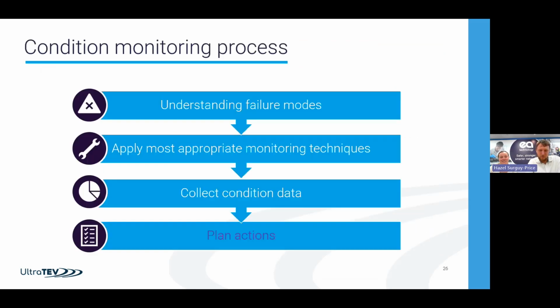The final and most important bit is to plan your actions. Generally you've got time to do this. If you've been doing regular measurements, you get a feel for how quickly something's changed, and the rate of change is a good indication of time to failure. We'll go through in future webinars and training how the width of the activity changes, and the number of pulses in the cycle, etc. There's evidence to show how quickly things are likely to fail. So you do need to plan them.